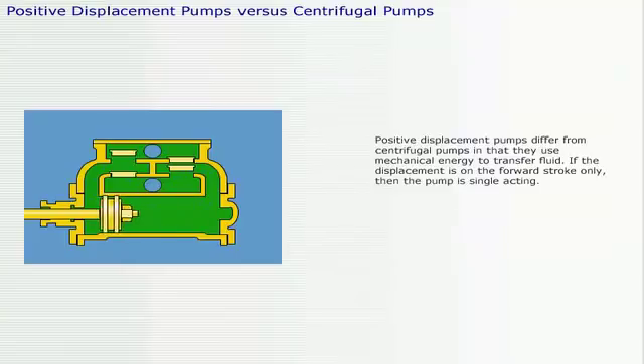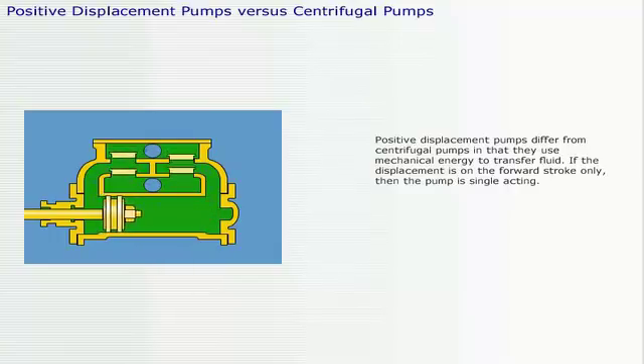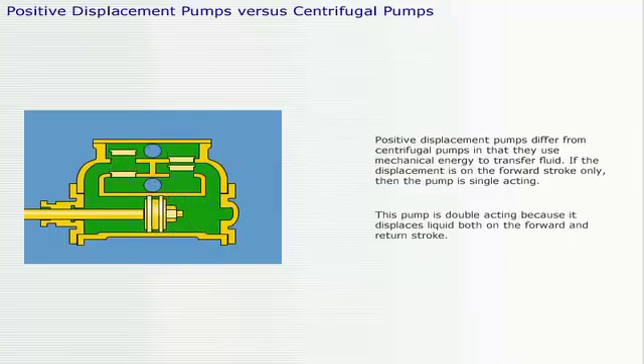Positive displacement pumps differ from centrifugal pumps in that they use mechanical energy to transfer a fluid. If the displacement is on the forward stroke only, then the pump is single acting. This pump is double acting because it displaces liquid both on the forward and return stroke.